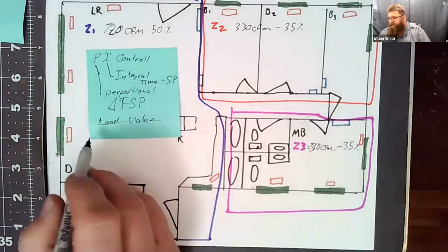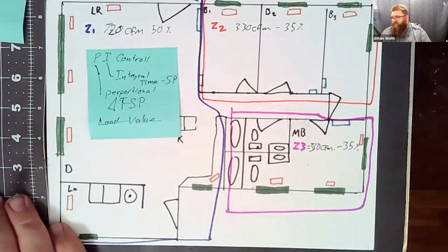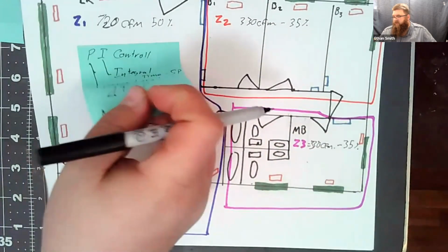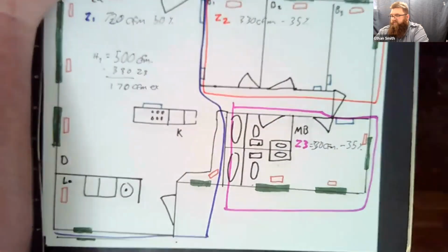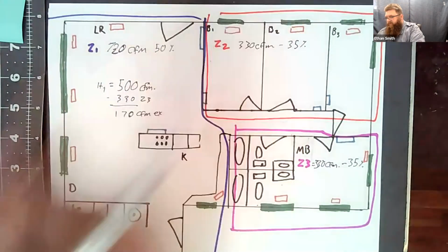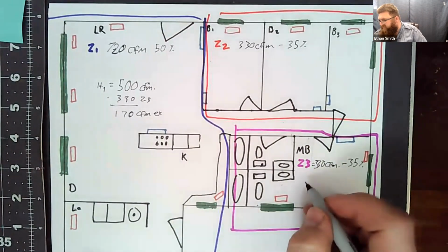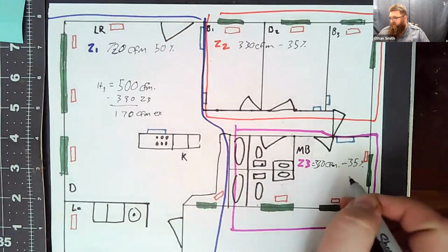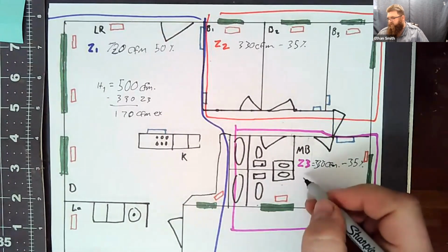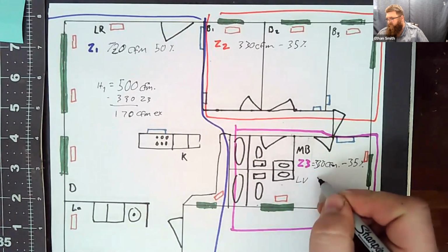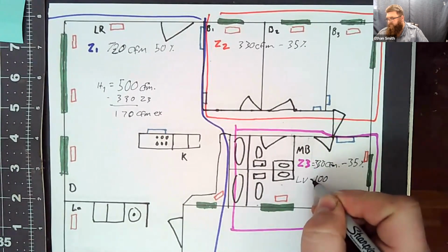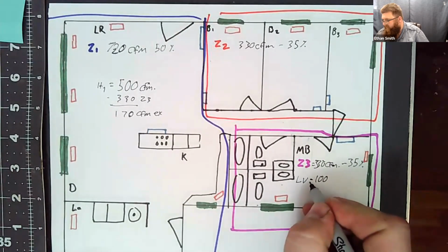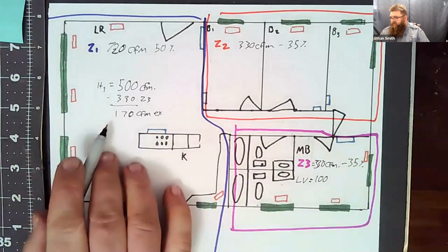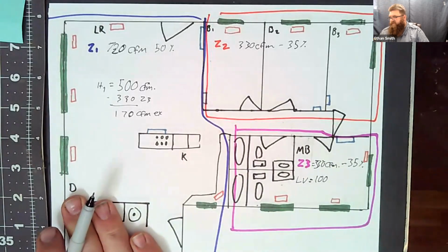Okay, so this load value number can help us out with our relief strategy, because now we can take a look at our zones and we can say zone 3 is the zone that's calling, and it's calling for first stage, which would be a load value of 100. Okay. But I've got a 170 CFM excess air problem. So let's go out to my other zones and see what their situation is.